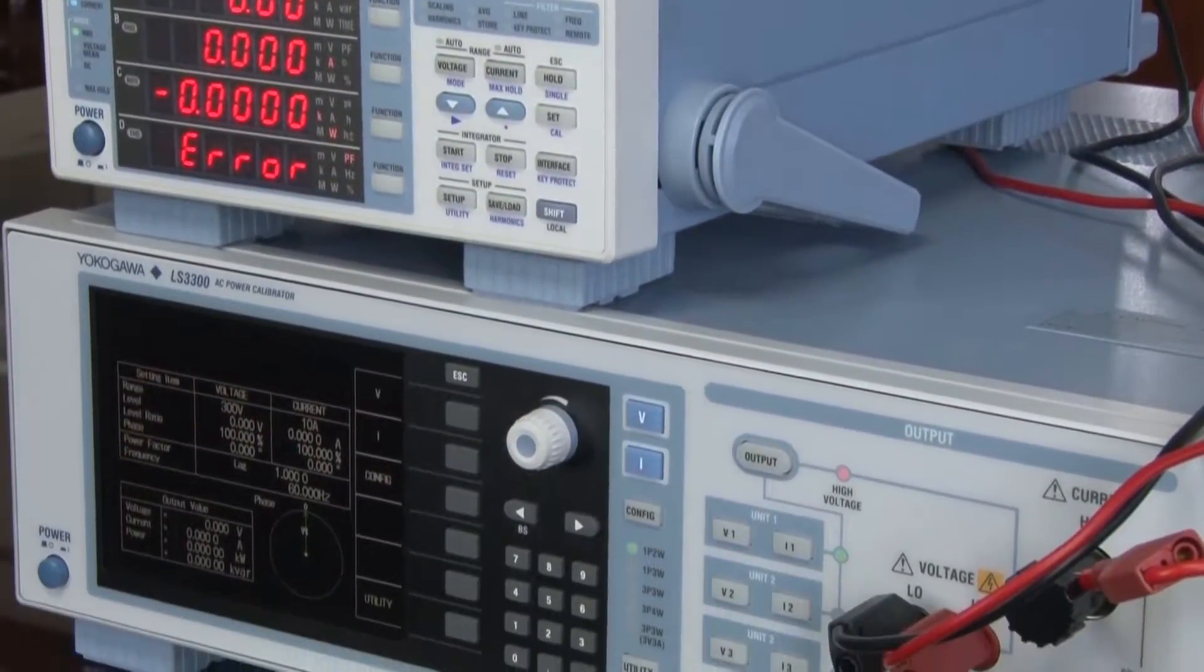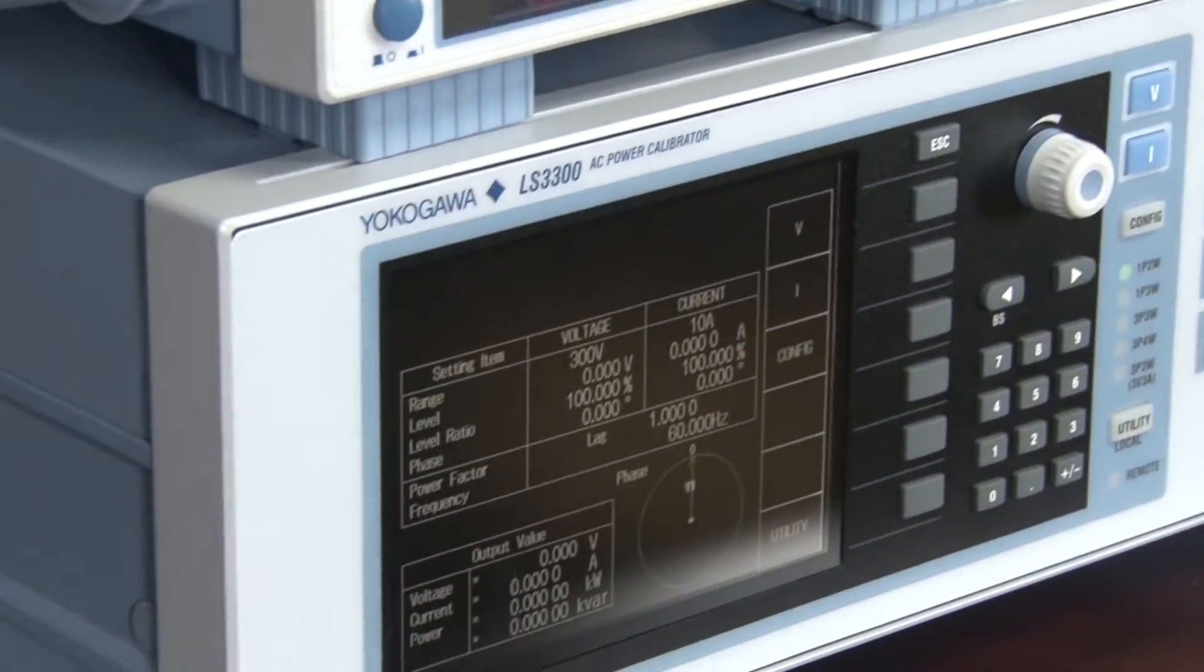Today I will be demonstrating how to perform a calibration test on the Yokogawa WT300 and 300E power analyzer series using the Yokogawa LS3300 AC power calibrator. The test accuracy ratio or TAR will be used to confirm the WT300's accuracy. The TAR will be discussed in further detail later in this video.